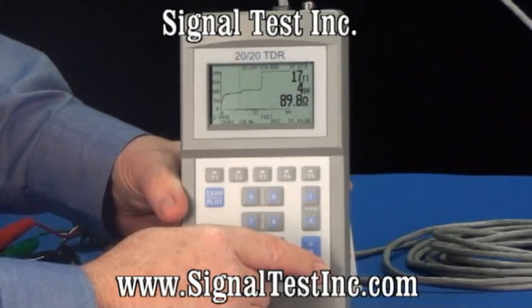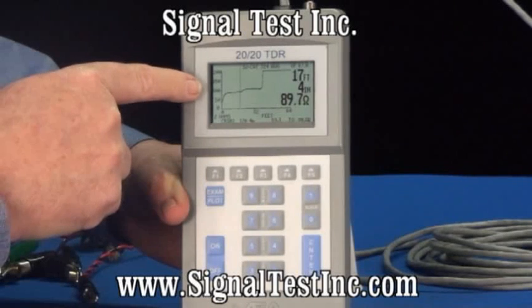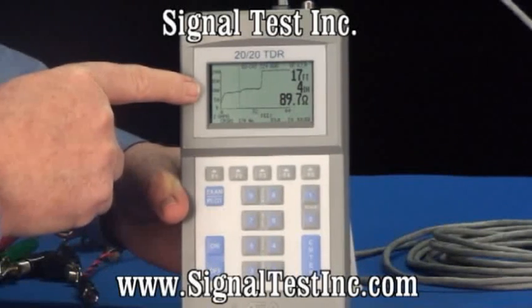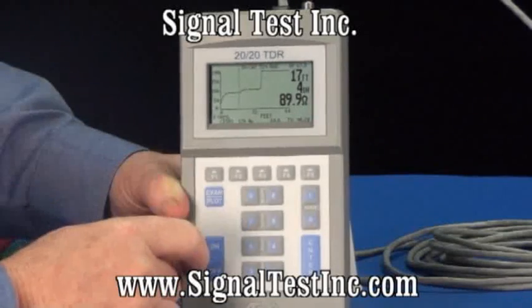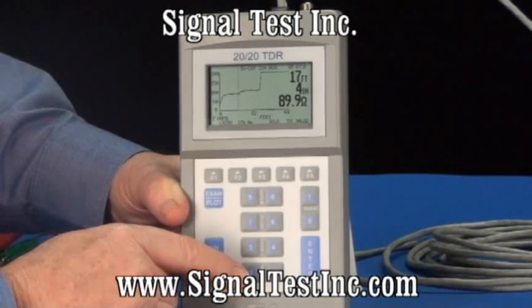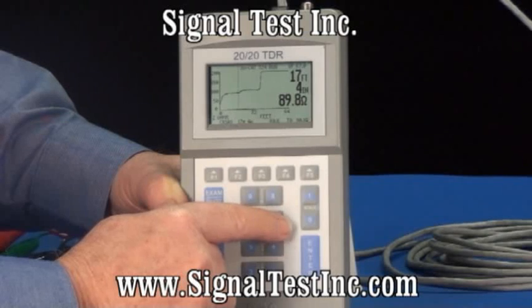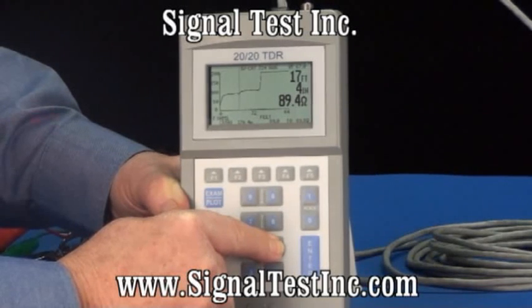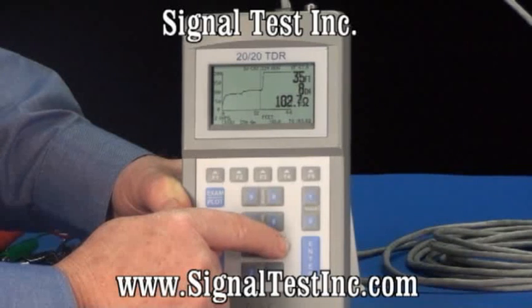When the view comes up, you'll notice the cursor is at 17 feet 4 inches. There's a defect in the cable there — it's actually what's called a split pair. The cable has had one white wire crossed with the other wire from another pair, and it's causing an impedance deviation. But that's not the electrical end of the cable. By pressing the cursor, we can go further out, and the electrical end of the cable is actually all the way out here at 35 feet 8 inches.